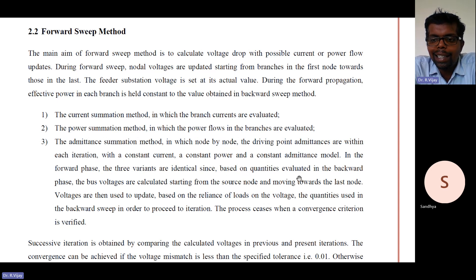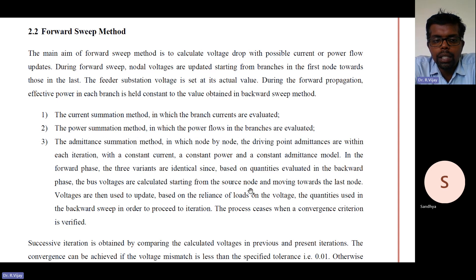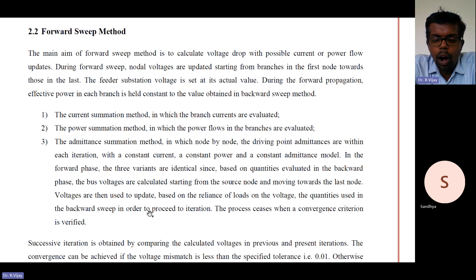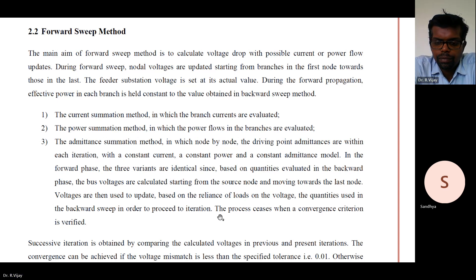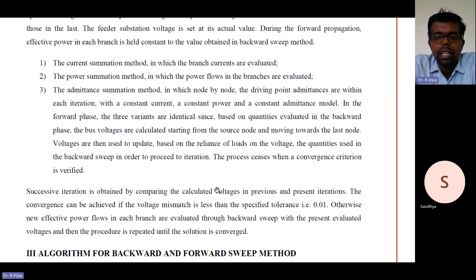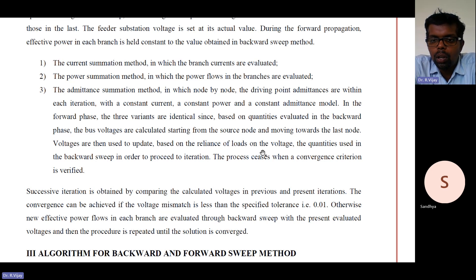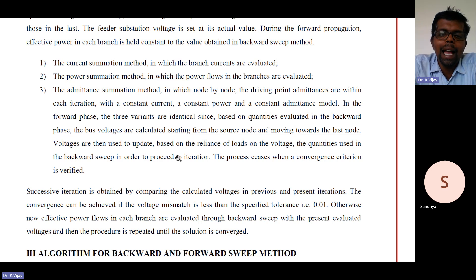Based on the quantities evaluated in the backward phase, the bus voltages are calculated starting from the source node and moving towards the last node. The voltages are then used to update, based on the loads, the quantities used in the backward sweep in order to proceed with the next iteration. The process ceases when the convergence criteria is verified.